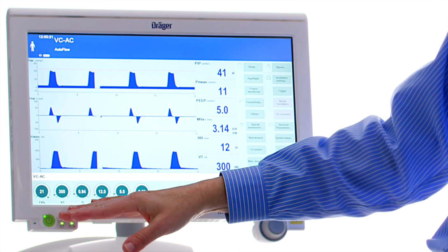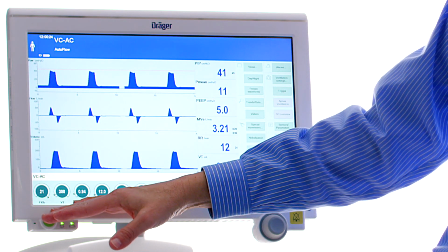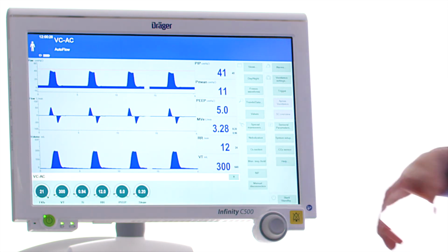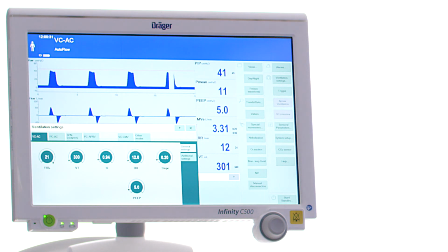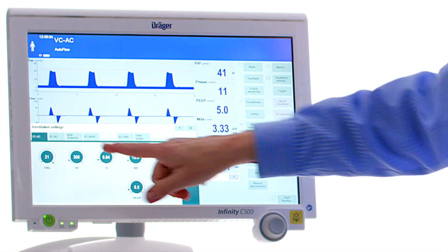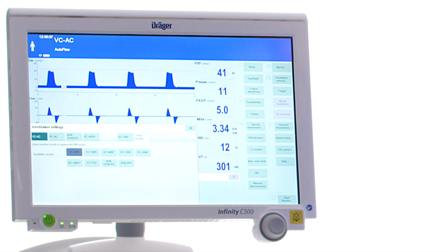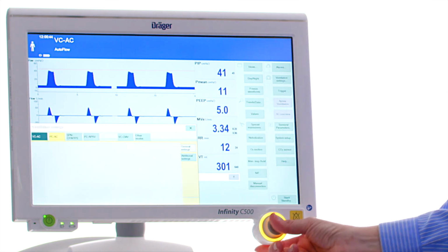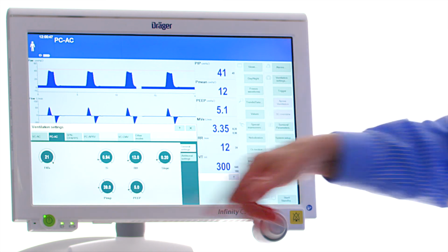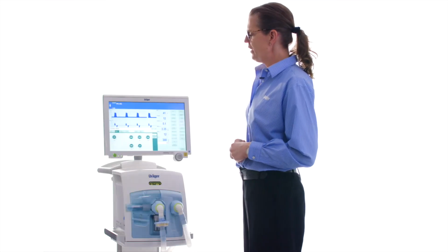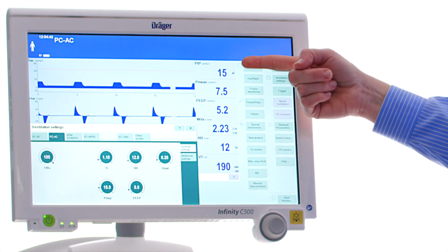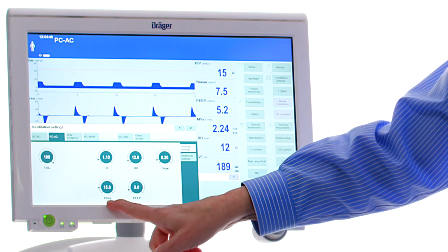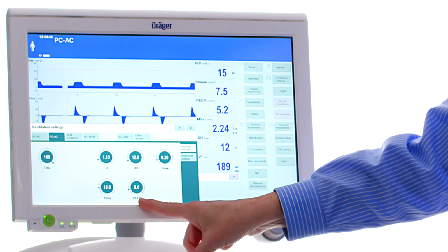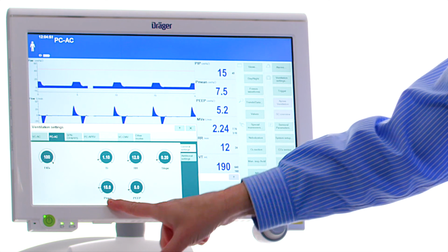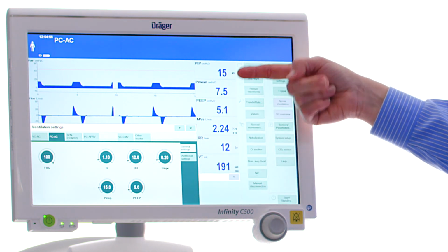We have access to make fast changes to our ventilation parameters down at the bottom, but to change our mode of ventilation, simply touch the mode that's displayed on the header bar. Again, you have configurable tabs for the modes that are used most often. I can go to Other and it will show me all the modes that the ventilator has. If I go to a pressure control mode, I'm now setting a pressure instead of a tidal volume. It's important to know on the Draeger ventilators, the pressure that you set is going to be the pressure that you get. The pressure that you set, P-insp on the Draeger ventilator, is inclusive of your PEEP. Notice that I have it set at 15 and my PIP is reading 15 as well.